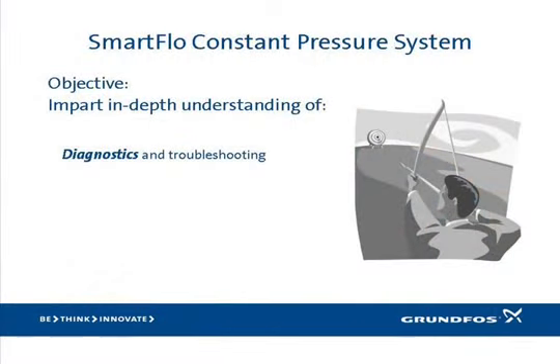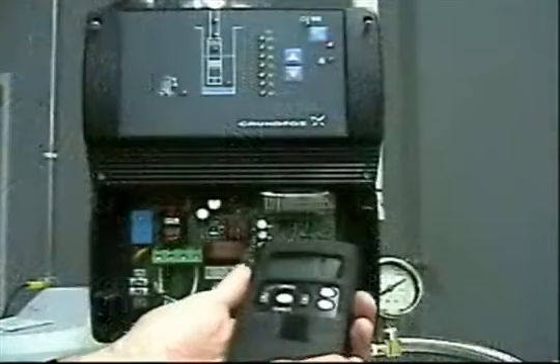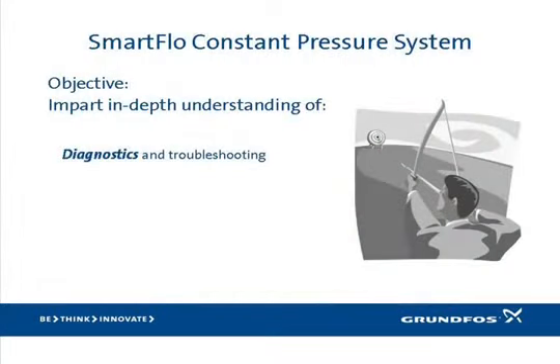The objective of this training module is to impart an in-depth understanding of the SmartFlo's built-in diagnostics along with simple troubleshooting techniques. We are going to focus on those powerful built-in diagnostics and learn how to read and interpret them. Both the SQE and the CU-301 are by definition computers, each capable of detecting and declaring a wide range of faults or abnormal operating conditions. The goal of this built-in intelligence is to protect the pump and motor from potential damage and extend its lifetime.